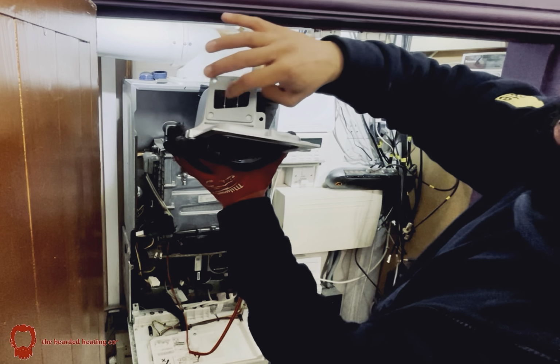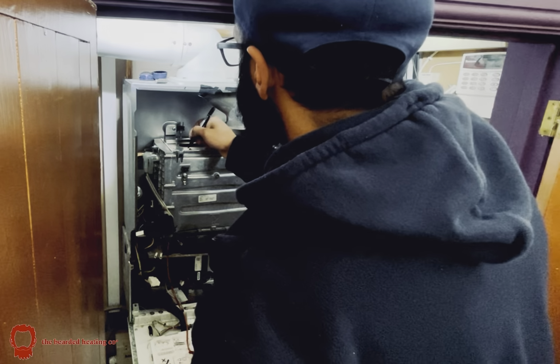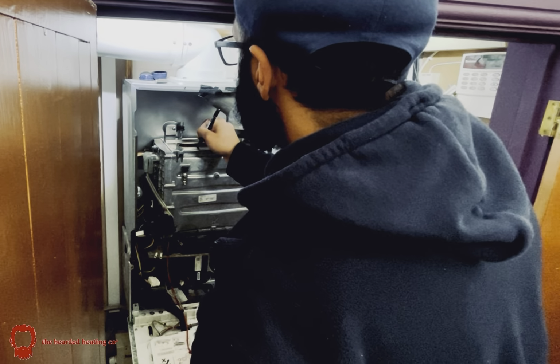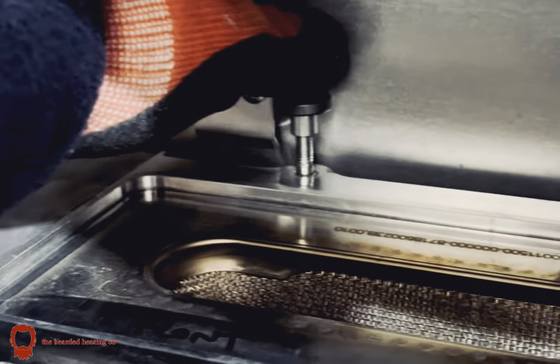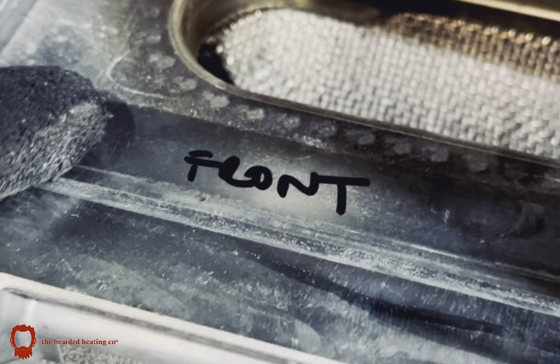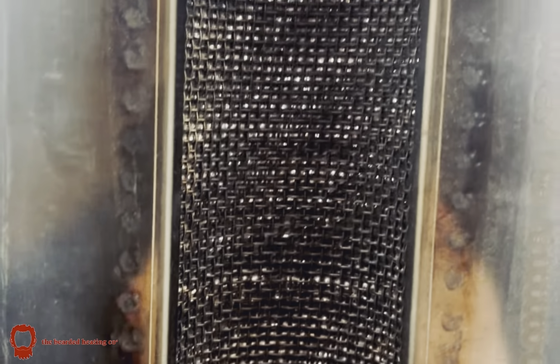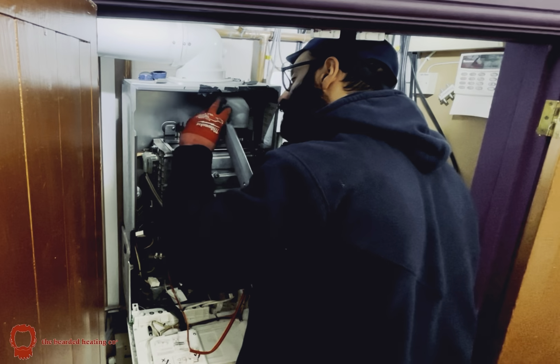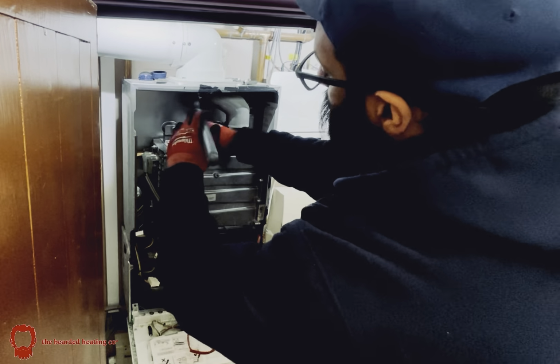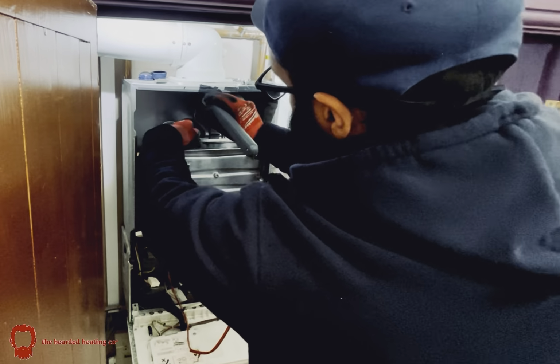Burner's out. I'm checking the one-way valve on the fan connection to make sure it's moving loosely. I wrote on the front of the burner itself to make sure I put it back in the right way. Here you can see the inside of the heat exchanger. It looks pretty dirty. I'm checking the burner to make sure it's not blocked. I did blow some air over it using my compressor. And now using the cleaning blade, I'm cleaning the inside of the heat exchanger.